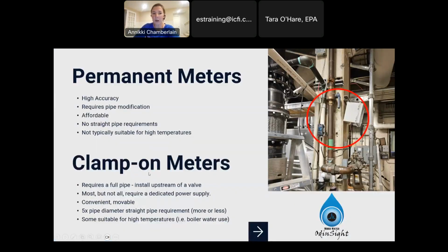Okay, so here we are with clamp-on meters. Again, I love these, they're so convenient. Here's a clamp-on meter on a cooling tower blowdown, and then the brains are up here, so pretty out of the way. So nuances with these. They require a full pipe. The pipe has to be full, so you have to be upstream of a valve, right? So the blowdown valve, you can't see it here, is down here. So that pipe is always full.